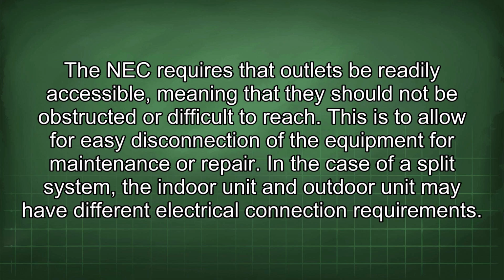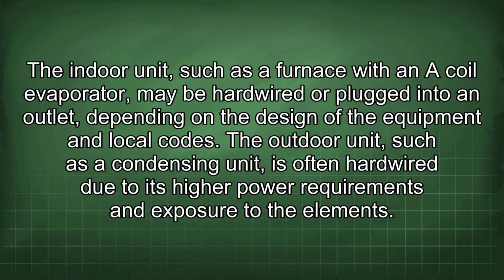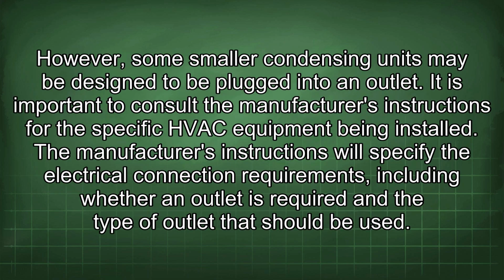In the case of a split system, the indoor unit and outdoor unit may have different electrical connection requirements. The indoor unit, such as a furnace with an A coil evaporator, may be hardwired or plugged into an outlet depending on the design of the equipment and local codes. The outdoor unit, such as a condensing unit, is often hardwired due to its high power requirements and exposure to the elements. However, some smaller condensing units may be designed to be plugged into an outlet. It is important to consult the manufacturer's instructions for the specific HVAC equipment being installed. The manufacturer's instructions will specify the electrical connection requirements, including whether an outlet is required and the type of outlet that should be used.